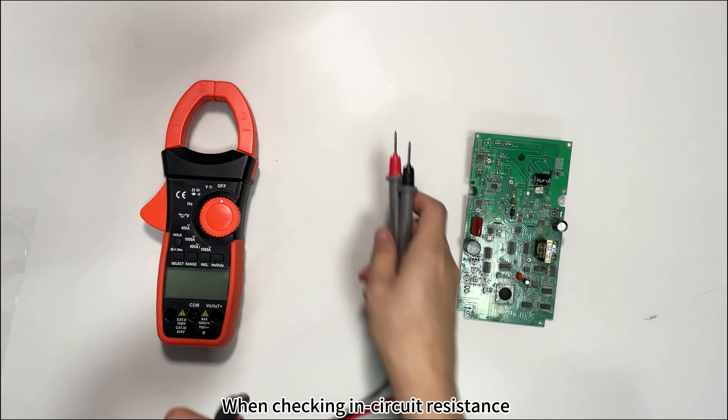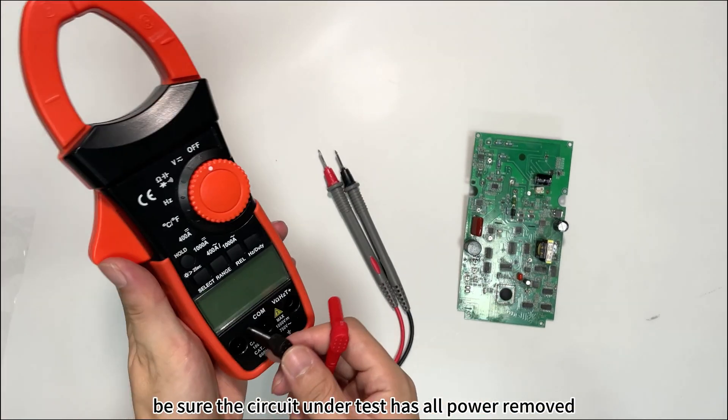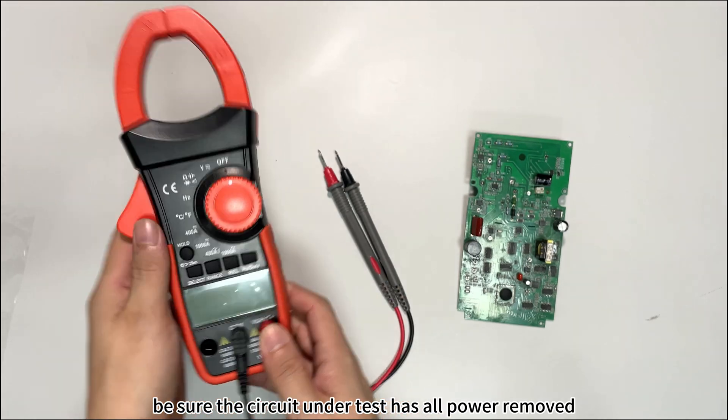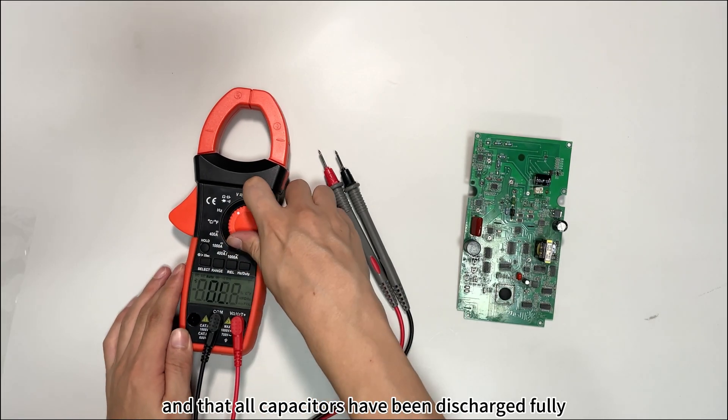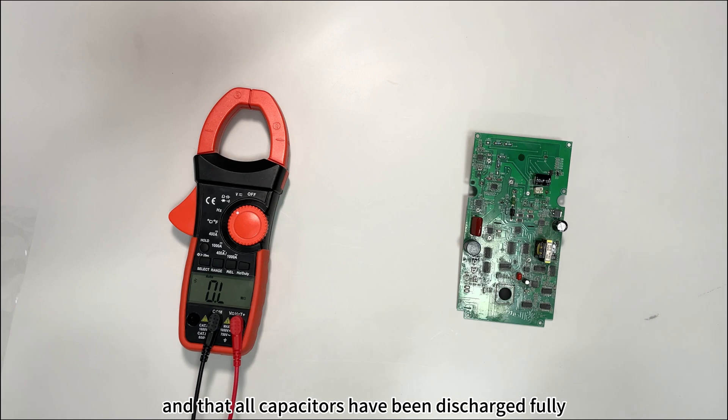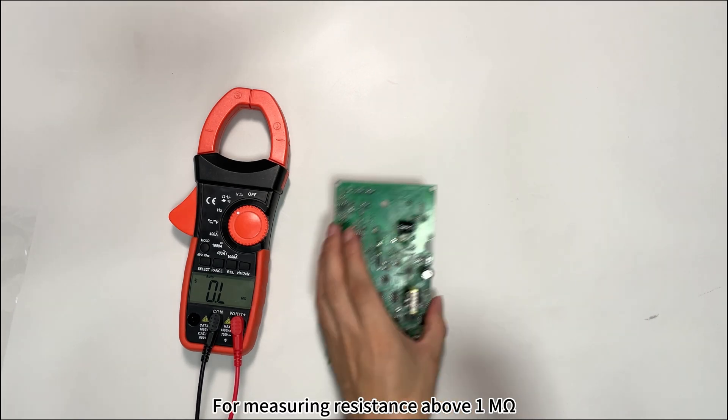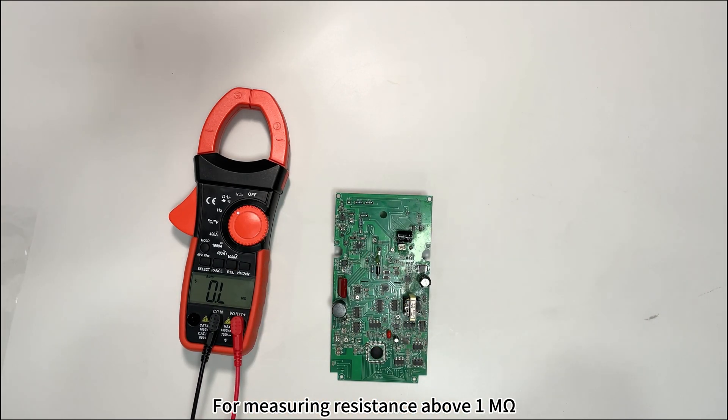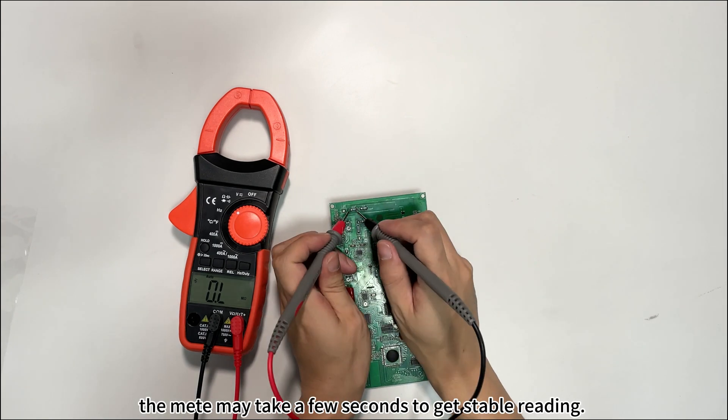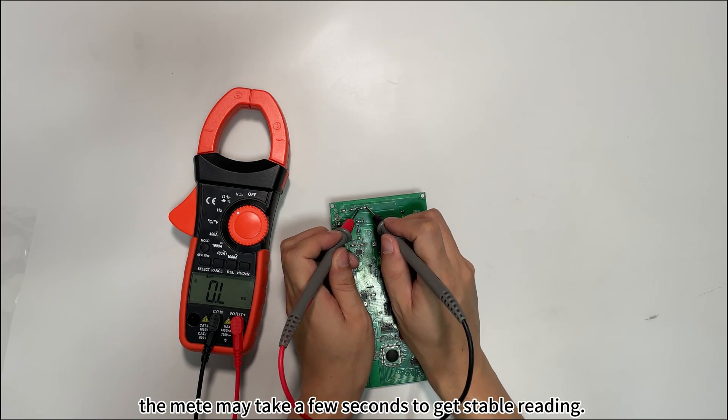When checking in-circuit resistance, be sure the circuit under test has all power removed and that all capacitors have been discharged fully. For measuring resistance above one megaohm, the meter may take a few seconds to get a stable reading.